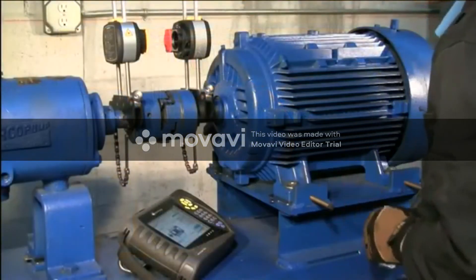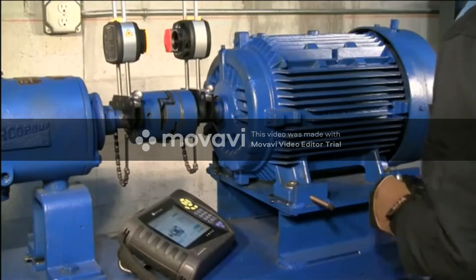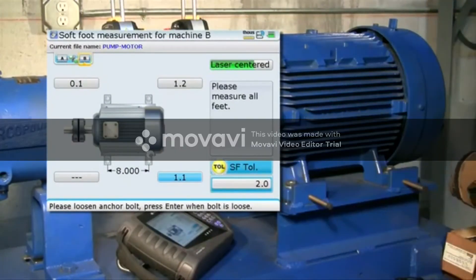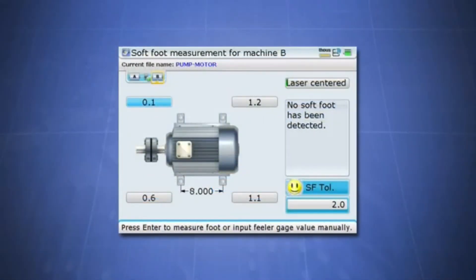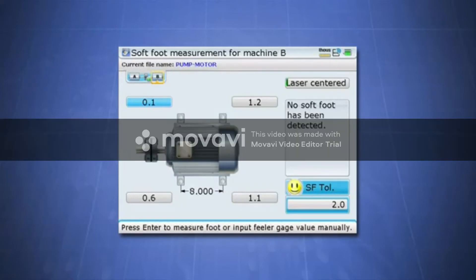When you started the rough alignment, you already set up the sensor and laser on the shafts, so there's no need to break out any additional equipment. Let's now begin our final soft foot check. Simply loosen one hold down bolt with the other three feet tight and let the Rotalign Ultra measure the shaft deflection. Then re-tighten the bolt. Move to the next bolt and repeat this process for the remaining bolts. The numbers displayed are the calculated values for the shaft movement at each hold down bolt position. If your displayed values are less than 2 mils, you have no significant soft foot and you can proceed with the rest of the alignment.